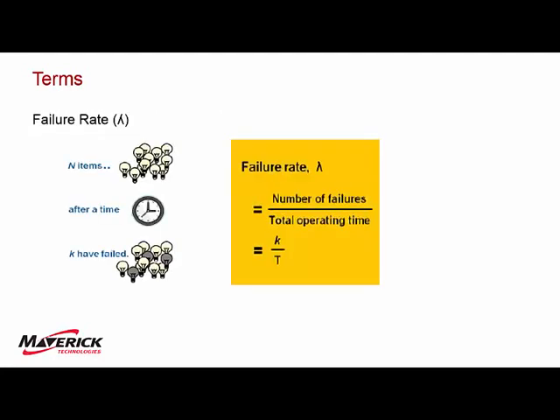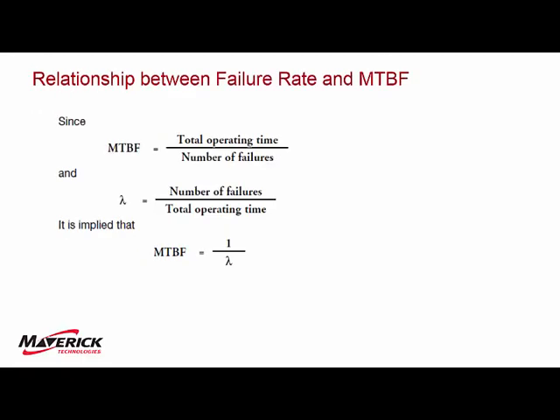Another term is failure rate. Failure rate is generally used for more components. Say you have 100 light bulbs and over 1,000 hours, five of them have failed - that's a failure rate. How many failures you had over your total operating time. These are kind of two big terms. They mean the same things but in different ways. They're reciprocal to each other. MTBF is total operating time divided by the number of failures, and failure rate is number of failures divided by the total operating time. So it's implied that they're reciprocal, which is how I'd use that 75 MTBF to give you the failure rate, which is what you need for initiating events.